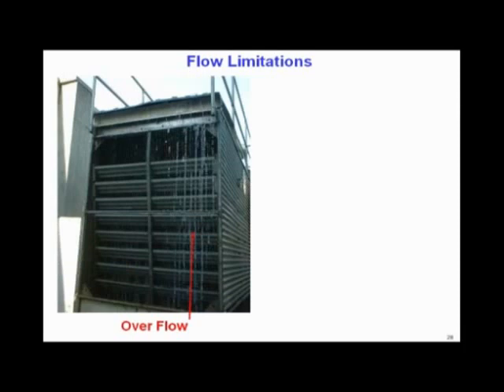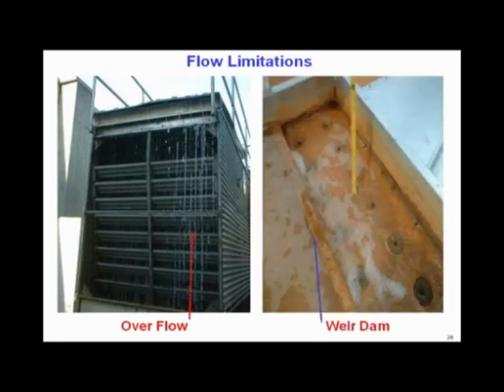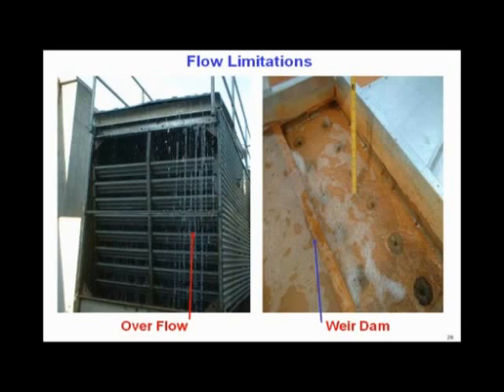Putting this all together with flow limitations: on the left-hand side you can see overflow — water is just going off the hot decks down the side of the tower, which is a waste, extra pumping cost, chemical cost, and in cold weather that tower is going to freeze. On the right-hand side, that's the weir dam on the hot deck itself — just a small piece of metal placed across the top of the hot deck to dam it up.